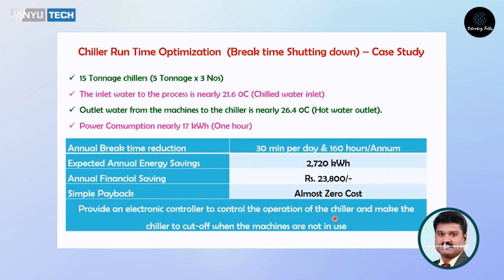Then automatically you can save 30 minutes of operation, and yearly it's going to be 160 hours of operation. That can save 2,700 units of energy. If you convert that into a cost, it's going to be around 24,000 rupees. Almost zero cost, you just need an electronic controller. Within 3 days they implemented this. They got a good result.